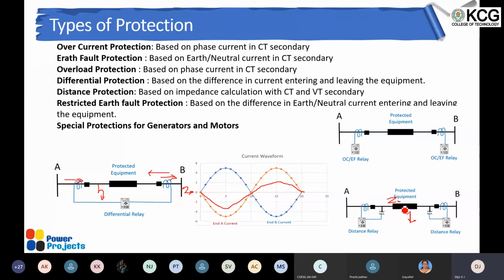Basically this relay will calculate the impedance from the voltage and current values it gets, and based on the impedance value we give a setting. Let's assume that 80% of the line has some impedance. So we'll set the impedance relay with 80%, that is, the setting as 0.8 ZL. Up to 80% of the line, this relay is going to see the fault in the forward direction, and it's going to give a trip command to this breaker. So that's the distance protection.